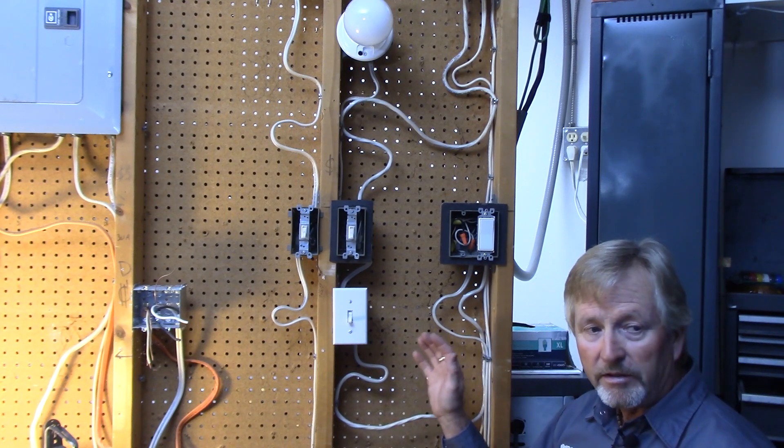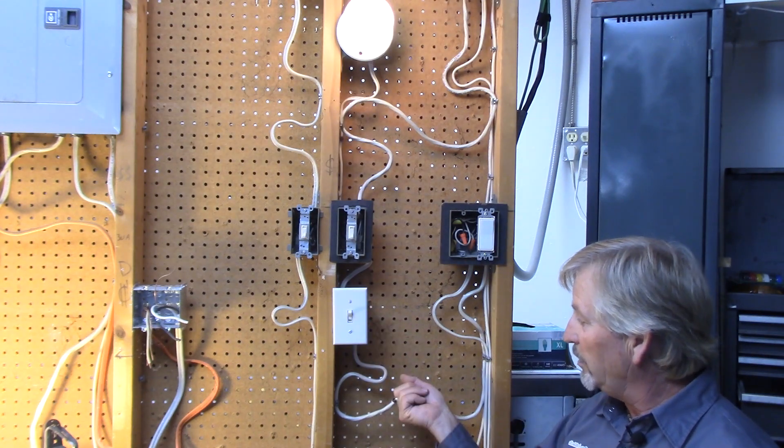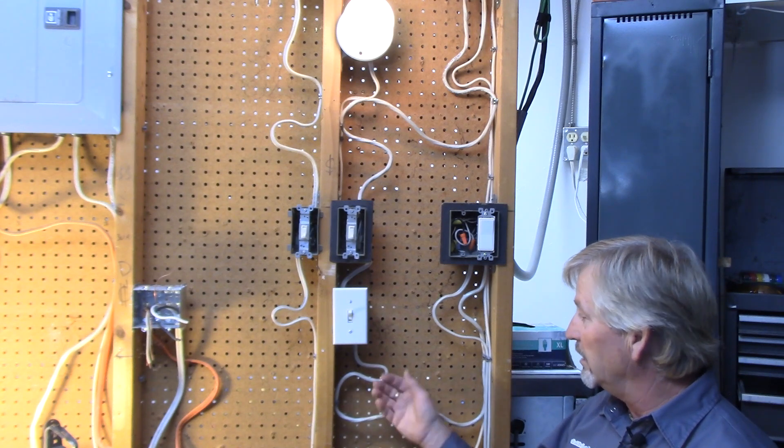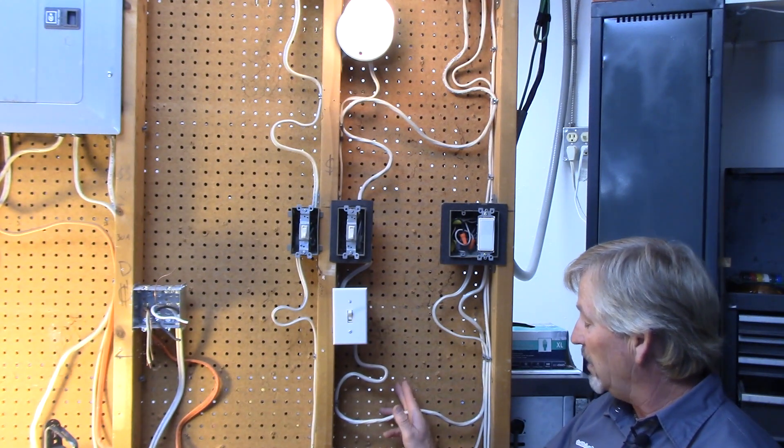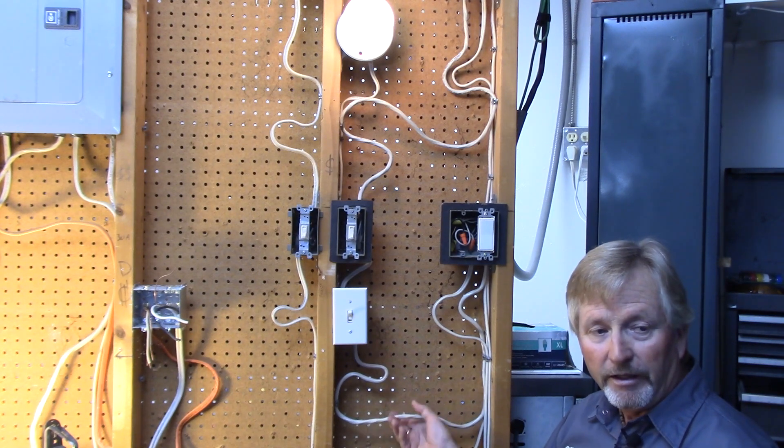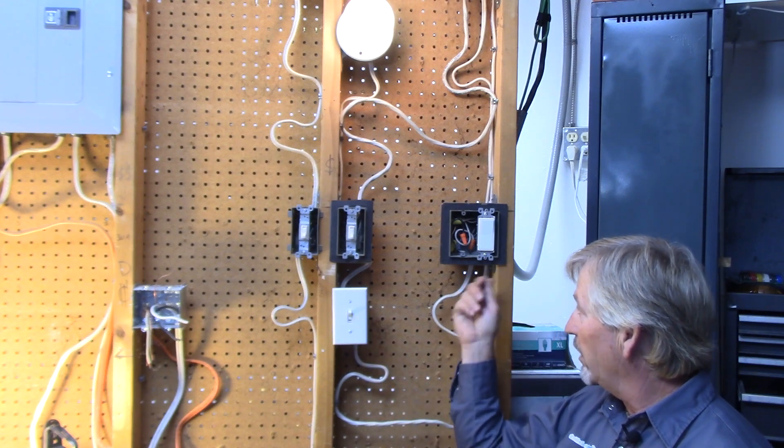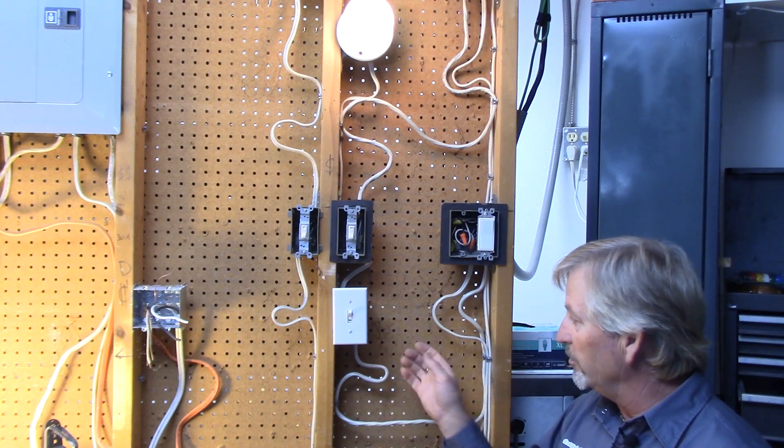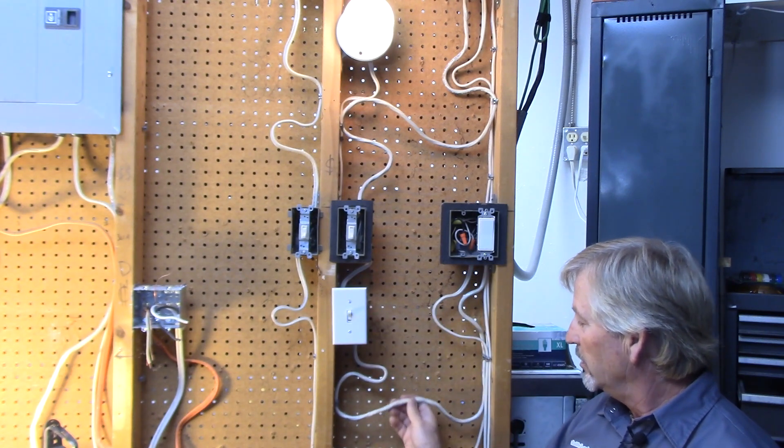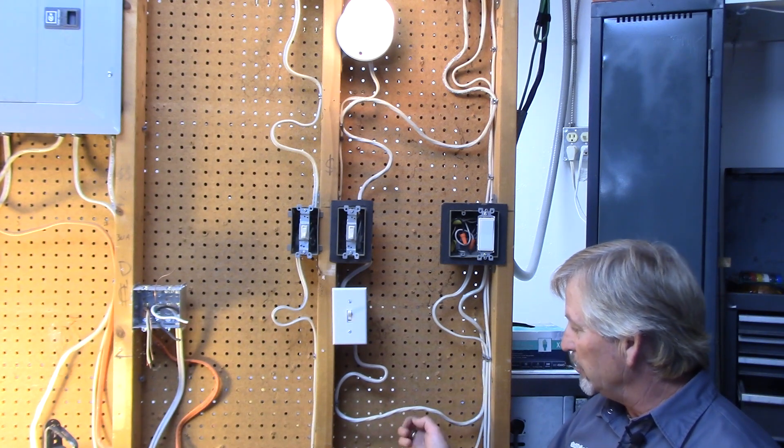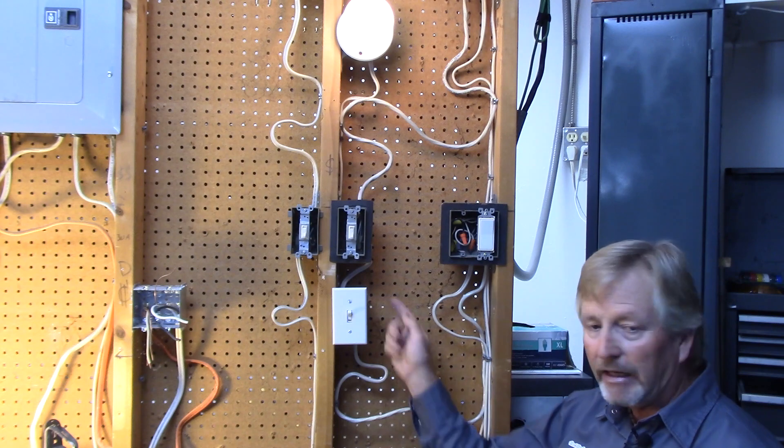So always remember to add a four way network, or to have a four way network, you have to start with a three way switch and you have to end with a three way switch. In between, you could put as many four way switches as you'd like. So the best way to do this would be, wherever your location might be, if you were lucky enough to have enough slack and that's where you wanted your new four way, you would just cut this wire, this cable. Put it into a box and put your four way here. But in all likelihood you're not going to have enough length. So you would have to shut off the power of course, undo your splices, pull the three wire cable out of both boxes, and add a new length to wherever your new four way is going to go. So from the first three way to the four way, out of that four way with another three wire to the last three way. If you looked at the most simplest form, cutting this cable here, you would splice back your neutrals together and you would put your inputs on black and red coming from one switch, and your outputs on black and red heading over to the last three way in the network.